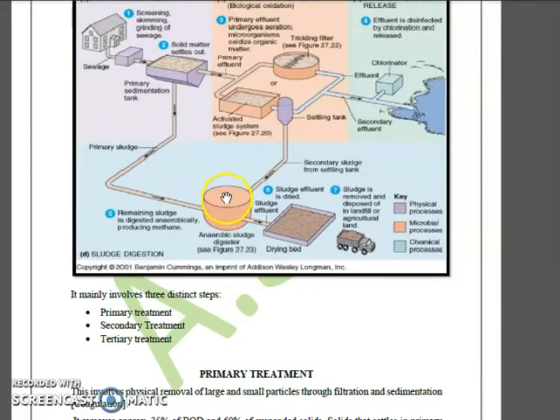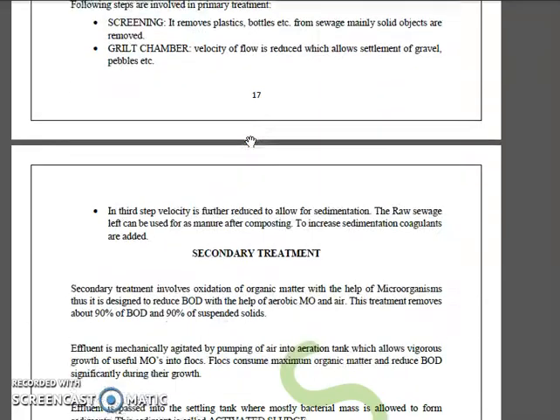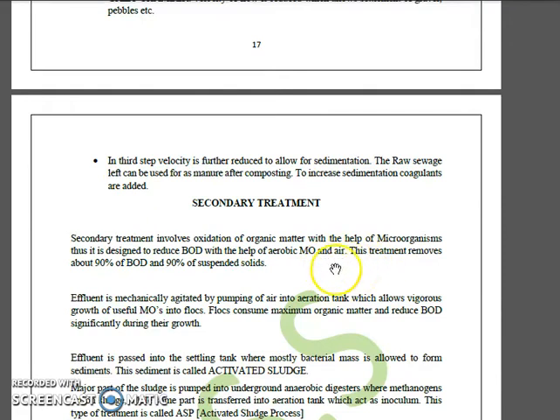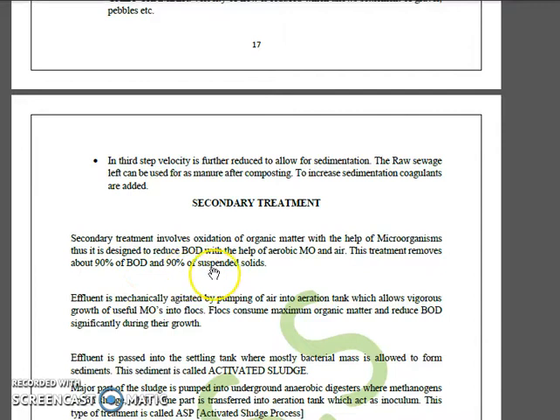Now moving to secondary treatment. The effluent from primary treatment goes to secondary treatment. Secondary treatment involves oxidation of organic matter with the help of aerobic microorganisms, and it is designed to reduce BOD. This treatment removes approximately 90% of the BOD and 90% of the suspended solids from the wastewater.